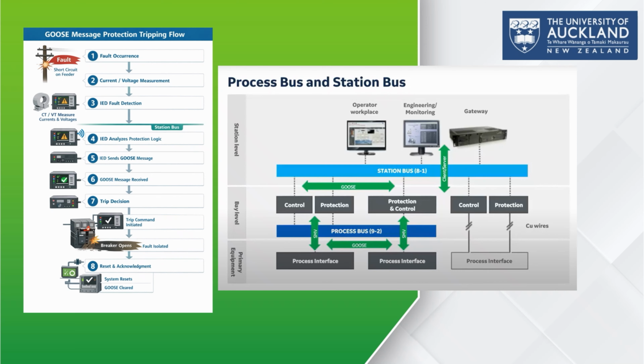So why is GOOSE important in a digital substation? Because it allows us to send fast protection controls like trip, close, interlock, and fault status within just a few milliseconds. In fact, IEC 61850 requires GOOSE to deliver these messages with an end-to-end delay of less than 4 milliseconds for critical protection functions. GOOSE also supports peer-to-peer communication among IEDs, enabling devices to interact without needing centralized control. This leads to systems that are more scalable, easier to maintain, and better prepared for automation and integration of distributed energy resources, right?